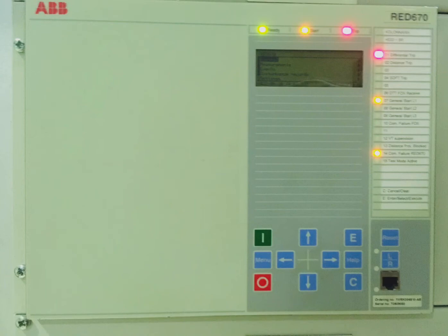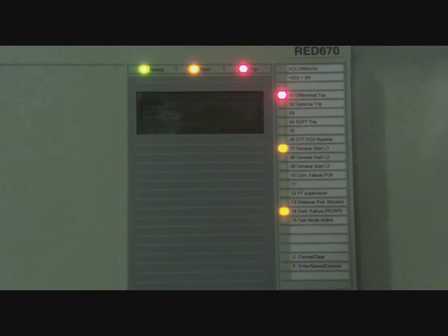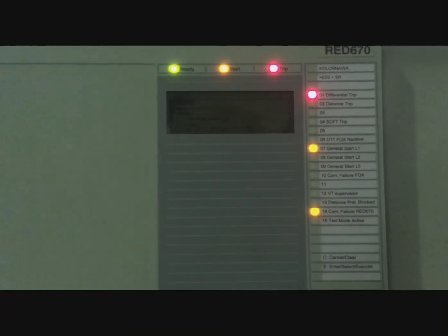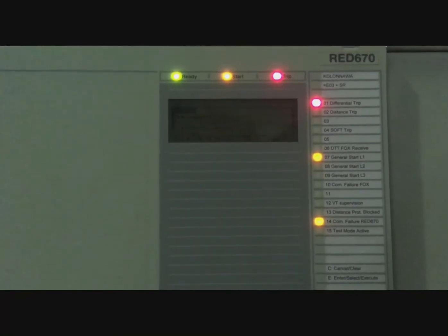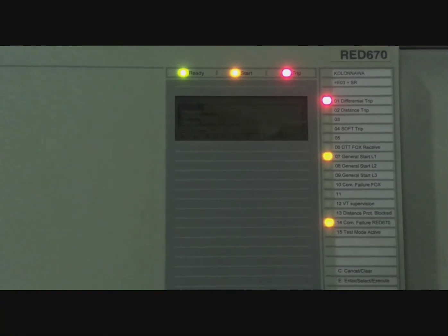Here you're going to discover how to reset this IED RED 670 when it has alarm indications. You can see several alarms appear on this panel: red alarms are main alarms and yellow alarms are starting alarms.